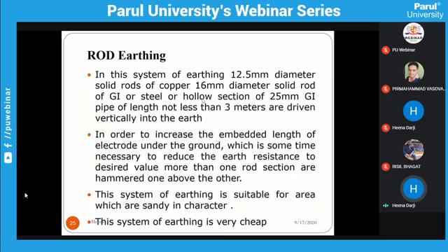Now rod earthing. In this system of earthing, 12.5 mm diameter solid rods of copper, 16 mm diameter solid rods of GI or steel, or hollow sections of 25 mm GI pipe of length not less than 3 meters are driven vertically into the earth. In order to increase the embedded length of the electrode under the ground, which is sometimes necessary to reduce the earth resistance to the desired value, more than one rod section is hammered one above the other. This system of earthing is suitable for areas which are sandy in character. This system of earthing is very cheap.